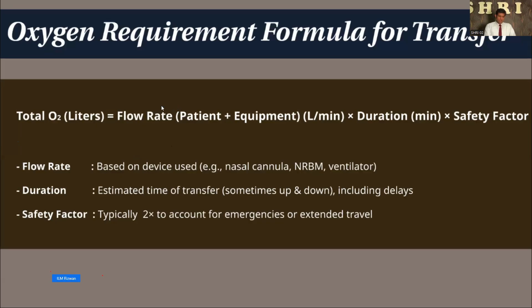So we know the flow rate depending on the patient requirement. And sometimes the patient is on a ventilator. Almost all modern ventilators are power driven, but there are a few, old ones or some devices, that are oxygen driven. They don't need any power supply, but the machine works because of the pressure of the oxygen, so some of the oxygen is used by the machine. Therefore, we should know what type of equipment we are using. We should have the flow rate requirement for the patient as well as the equipment's oxygen consumption.